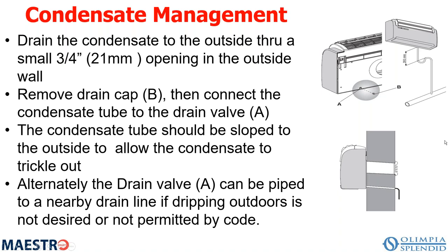So in the summertime, it's very rare for you to see any condensate coming out of the unit, because it's all evaporated. In the wintertime, however, if you're using it in a heat pump mode, that's a different story. We cannot pump the water or the condensate onto a coil. There's no benefit to that. So in the winter months, that pump is disabled. When you go into heating mode, that pump cannot be energized, and you would have to drain that defrost water out.